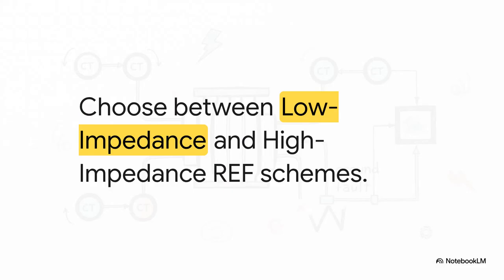Now, when you're setting up an RET615 relay to actually implement this, you've got two fundamentally different technologies wearing that same REF name. And let me tell you, mixing these up at the specification stage is one of the most common causes for commissioning delays in the whole industry. These two distinct solutions are LREFPDIF, which is our low impedance scheme, and HREFPDIF, the high impedance scheme. Let's break down exactly what each of these does.